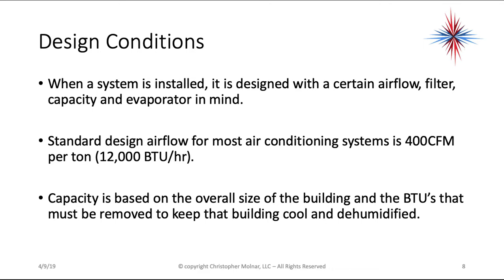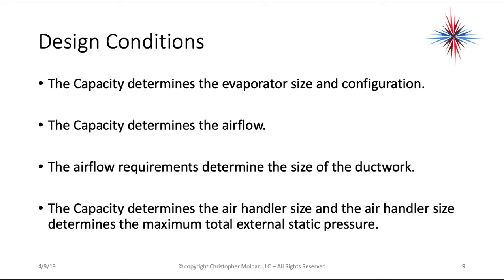Standard design airflow for most air conditioning systems is 400 CFM per ton, and a ton is 12,000 BTUs per hour of cooling capacity. Capacity is based on the overall size of the building and the BTUs that must be removed to keep it cool and dehumidified. The capacity determines the evaporator size, the airflow requirements determine the ductwork size, and the air handler size determines the maximum total external static pressure. Every air handler has a label that tells you the maximum total external static pressure that blower can handle at peak efficiency.